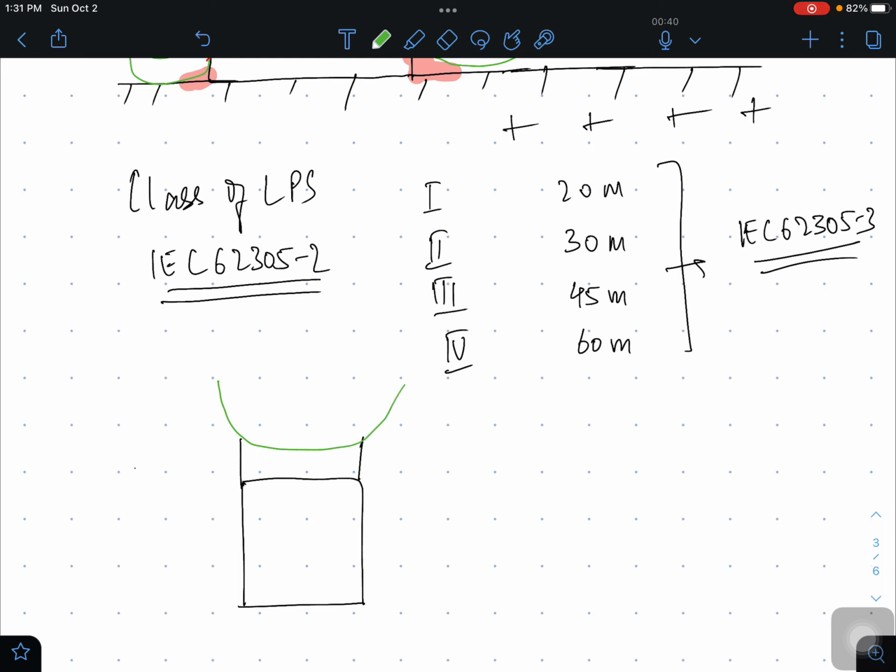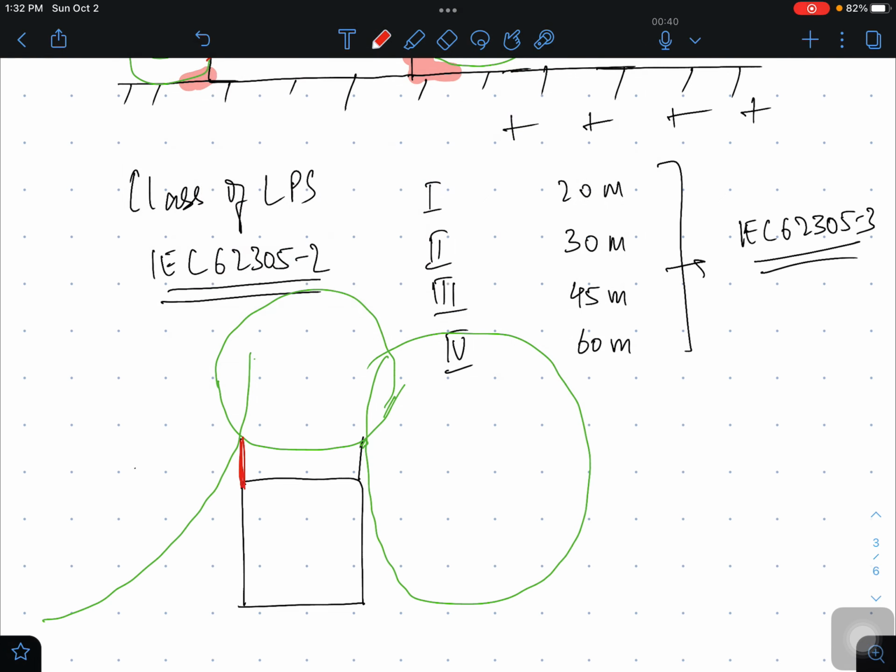This sphere will be there on the top of the 2 rods, it will not strike anything from the top. Then we will check from the side by rolling this, and we will see that there is no side strike here and there is no side strike here. So all the things are getting protected by providing these 4 rods on the top, 2 here.